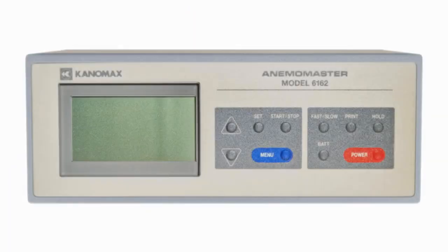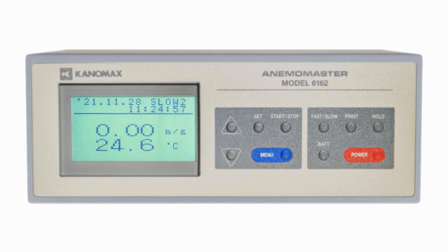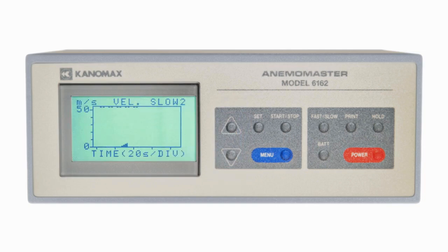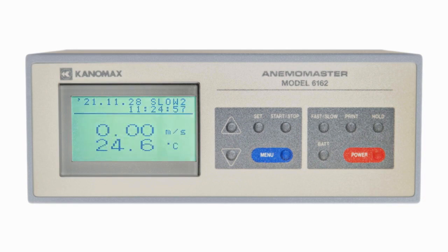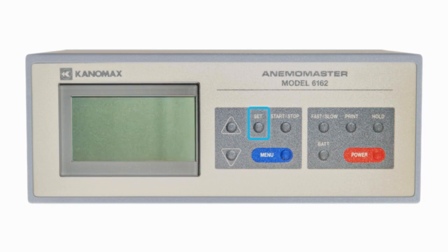On the front of the device, you'll find the LCD display and keypads. The left segment contains your scroll keys for navigating the device menus. Or, if you're at the monitor screen, pressing the down key will display the variation graph for air velocity. Pressing it again will switch the range for the graph, and pressing up will go back to the original screen. The Set key executes your selected items, while the Start/Stop key starts or stops a measurement, and the Menu key pulls up the menu for accessing other device functions.